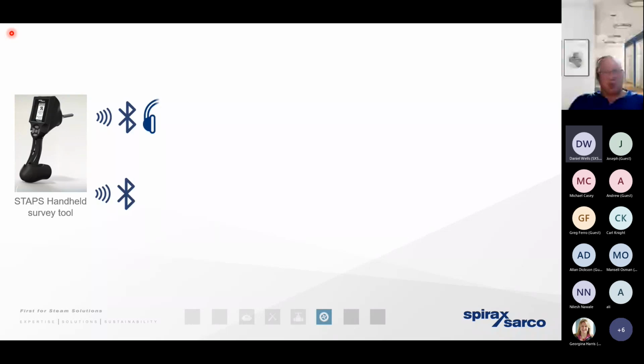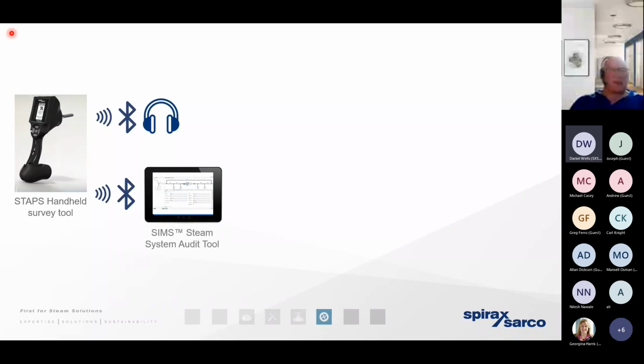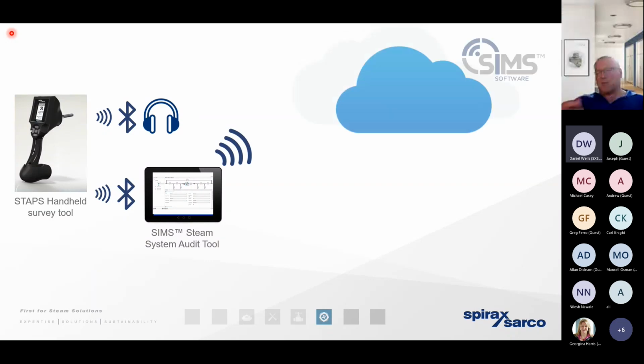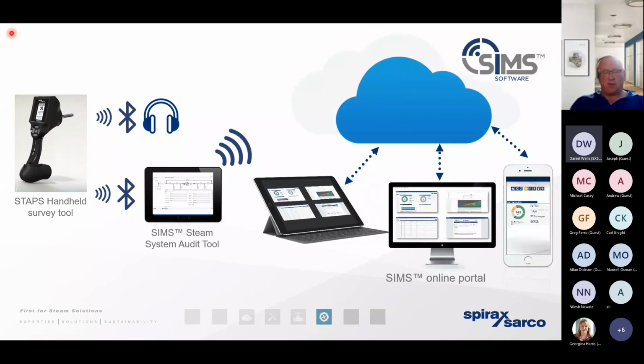So some form of connectivity is likely to be of key importance. Now, the vast majority of steam using sites will have a traditional steam trap survey of sorts. That's when the engineer will wander around site. He'll either scribble down notes or he'll be speaking into a dictaphone, identifying when a steam trap may be in the failed open or the failed closed position. It may take some weeks for that report to be compiled and then issued to the correct person on site.